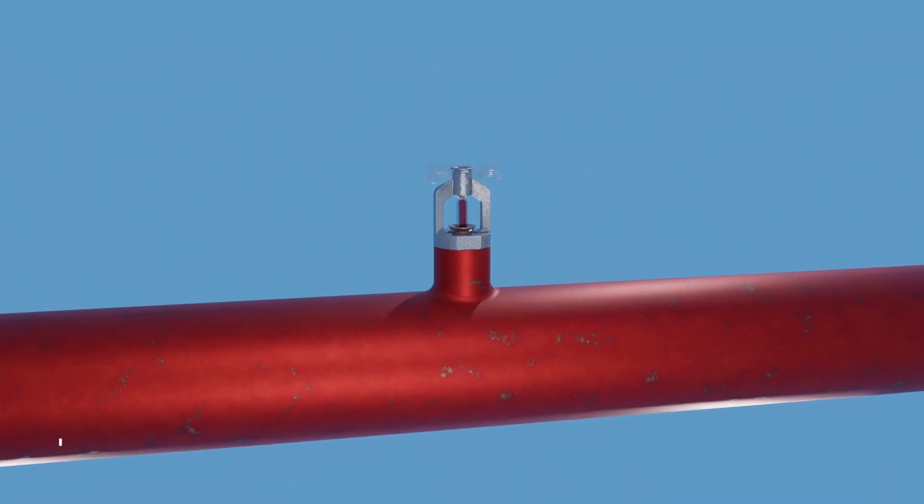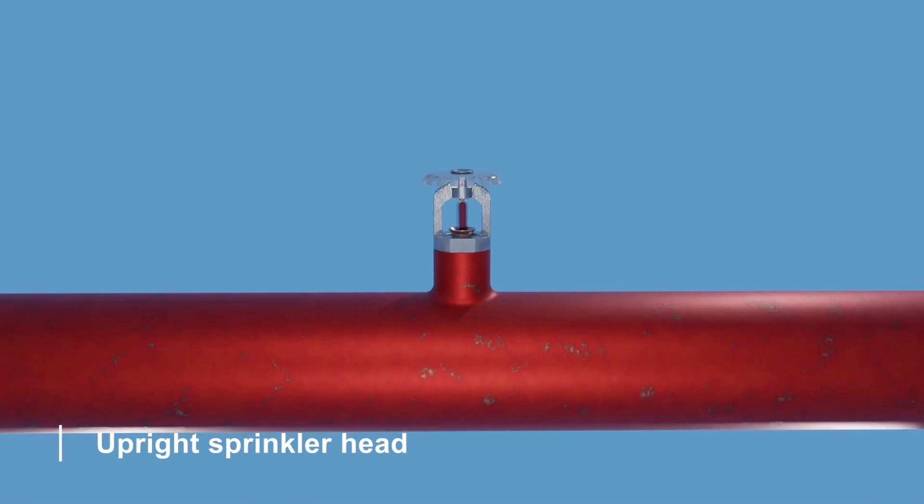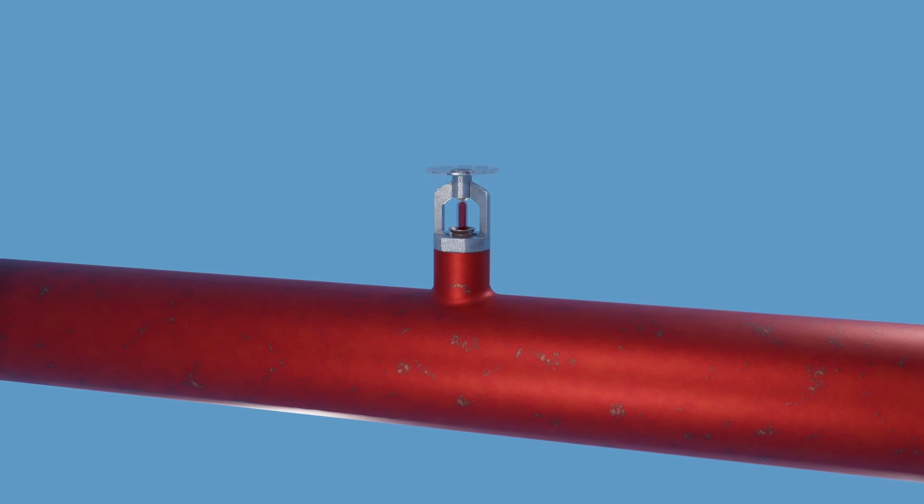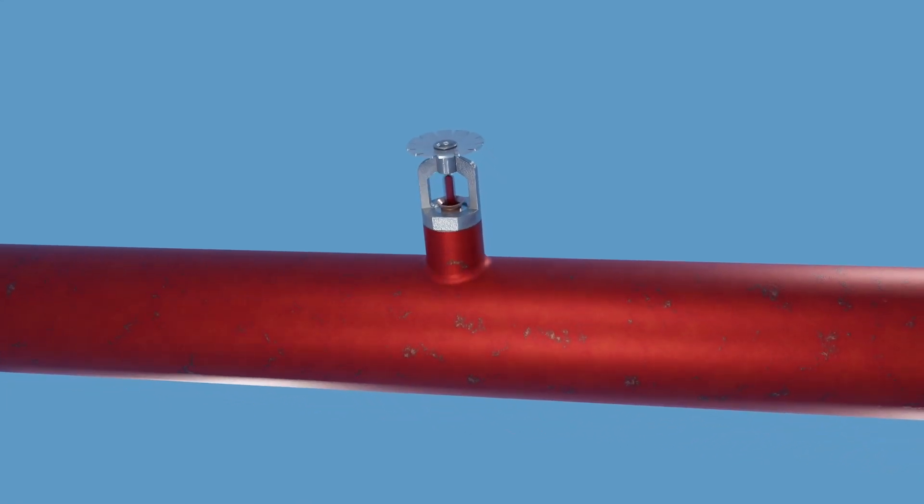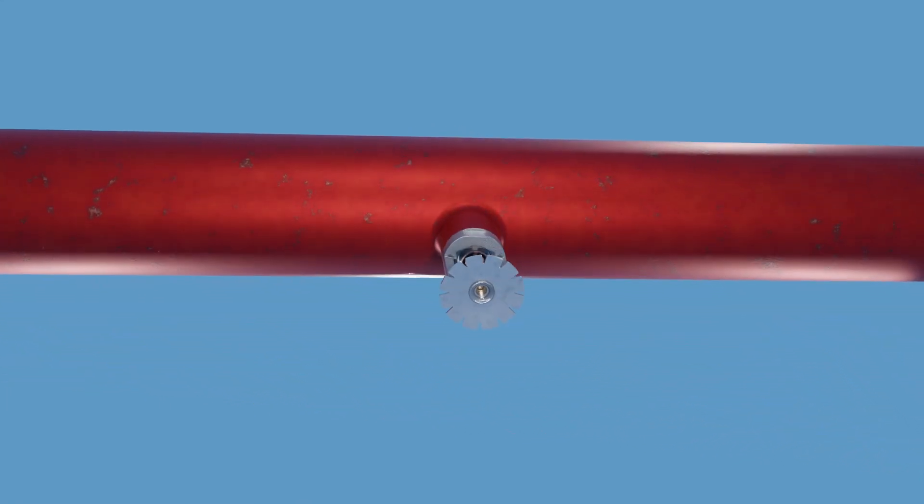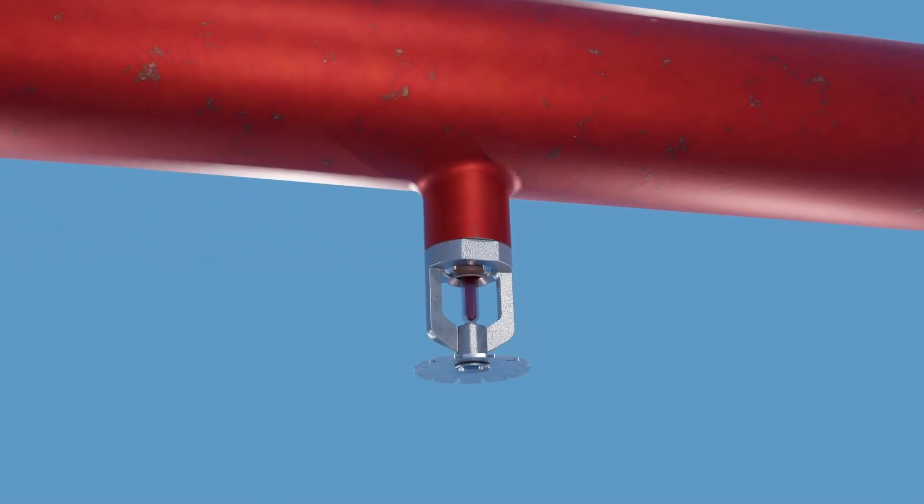The upright sprinkler head is installed with the deflector up and directs water upward and outward in a dome pattern using a concave deflector. Pendant sprinkler heads are used in areas where the ceiling is accessible, while upright types are commonly used where the ceiling is not accessible.